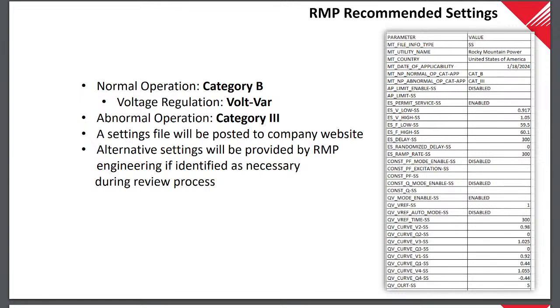Yeah, so this is new to us. What we're recommending is that volt-var setting — when you're measuring the voltage, it'll either consume or produce vars to raise or lower the voltage to keep it within those limits. If that's inadequate, if we set it to that and we're still seeing some disturbances, power quality issues, or reliability issues, then there are other options.